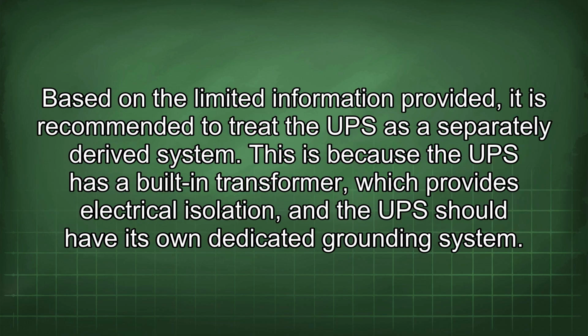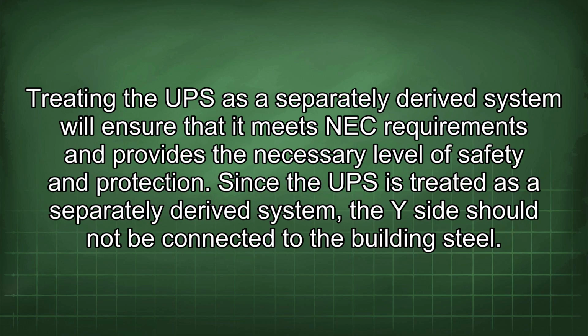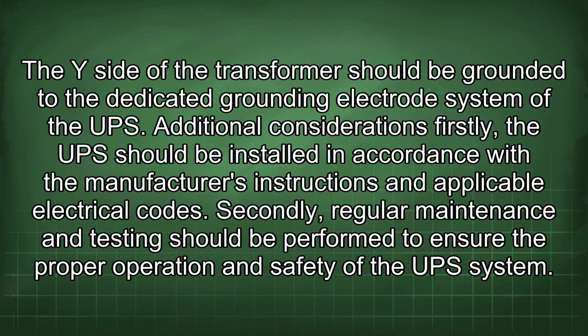Based on the limited information provided, it is recommended to treat the UPS as a separately derived system. This is because the UPS has a built-in transformer, which provides electrical isolation, and the UPS should have its own dedicated grounding system. Treating the UPS as a separately derived system will ensure that it meets NEC requirements and provides the necessary level of safety and protection. Since the UPS is treated as a separately derived system, the Y side should not be connected to the building steel. The Y side of the transformer should be grounded to the dedicated grounding electrode system of the UPS.